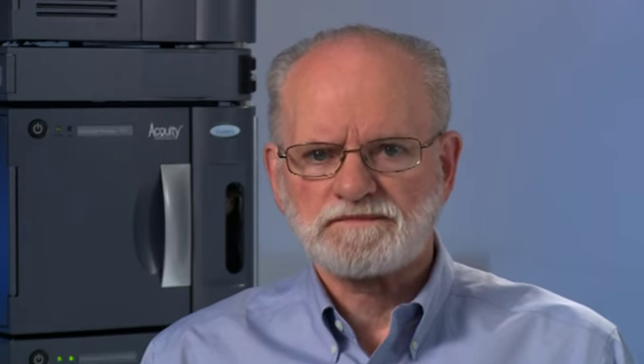Long ago, it became customary instead to prepare buffers from concentrated stocks of an acid and its salt, or a base and its salt. Specified volumes are mixed and the pH is checked and adjusted using the meter. When pH is iteratively adjusted for the best separation, a pair of buffers at low and high ionic strength must be prepared for each experiment. When four solvent pumps became available for HPLC, we found that we could simplify this process by using the pump to proportion on demand. We called this technique auto-blend, using the four solvent lines as an acid, a base, a salt, and water.